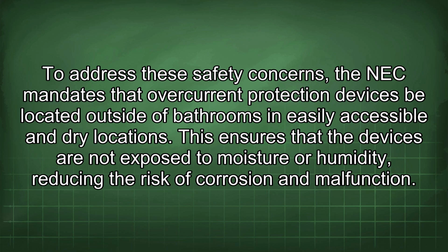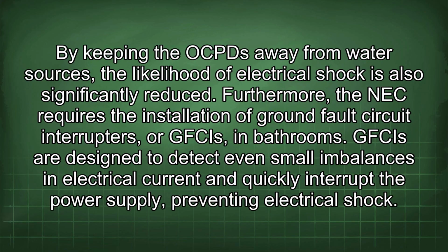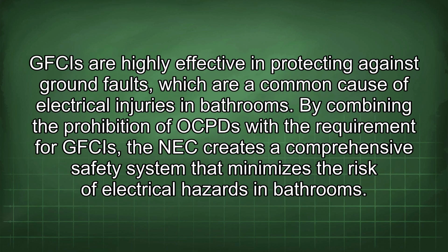To address these safety concerns, the NEC mandates that overcurrent protection devices be located outside of bathrooms in easily accessible and dry locations. This ensures that the devices are not exposed to moisture or humidity, reducing the risk of corrosion and malfunction. By keeping the OCPDs away from water sources, the likelihood of electrical shock is also significantly reduced. Furthermore, the NEC requires the installation of ground fault circuit interrupters, or GFCIs, in bathrooms. GFCIs are designed to detect even small imbalances in electrical current and quickly interrupt the power supply, preventing electrical shock. GFCIs are highly effective in protecting against ground faults, which are a common cause of electrical injuries in bathrooms. By combining the prohibition of OCPDs with the requirement for GFCIs, the NEC creates a comprehensive safety system that minimizes the risk of electrical hazards in bathrooms.